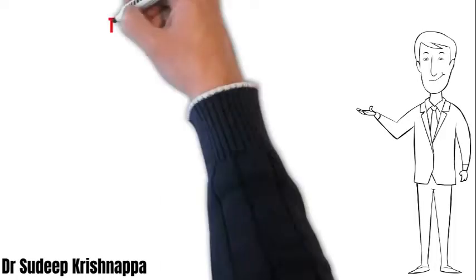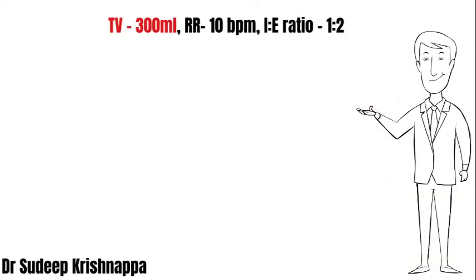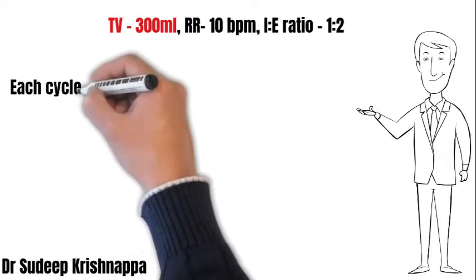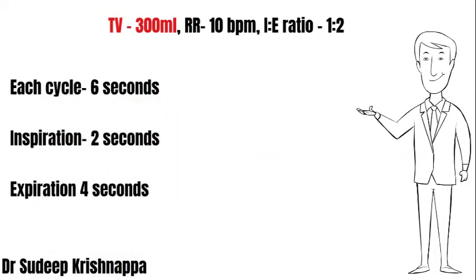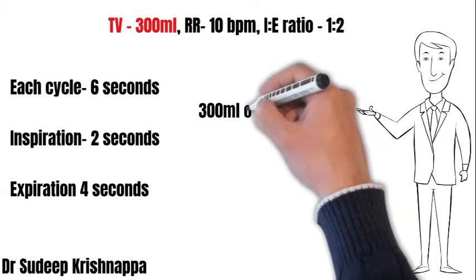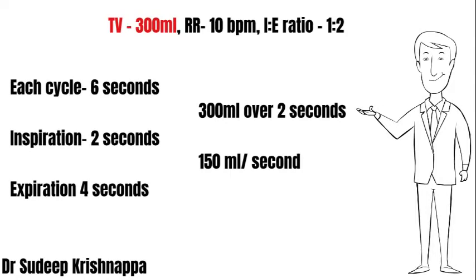We now move on to the third scenario: we reduce the tidal volume to 300 mL, keeping the respiratory rate and I:E ratio the same. The duration of each cycle remains 6 seconds, with inspiration of 2 seconds and expiration of 4 seconds. The tidal volume of 300 mL must be inspired over 2 seconds, translating to a flow rate of 150 mL per second.